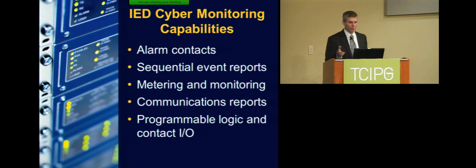There's sequential event reports, and we've used those from the power system side, day in and day out. They monitor contact input statuses, output statuses, anytime something changes within the, we call it the relay word bit, but any of the status for protection elements all get logged in there. They also log stuff like power up, power down, or settings changes. So it's really like the power engineer's version of a syslog. And those things are inherent in many, many IEDs at the substation level.